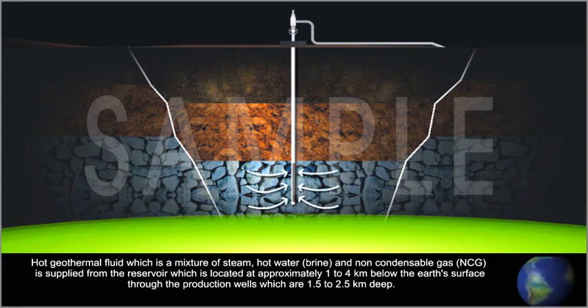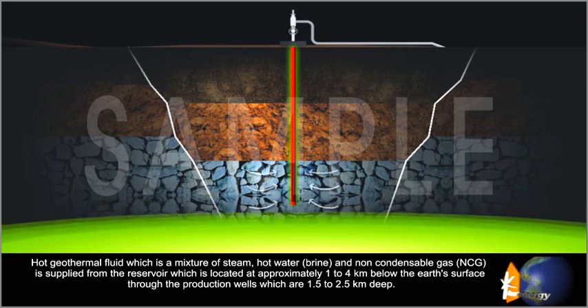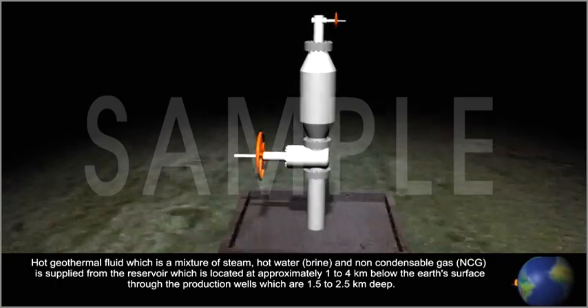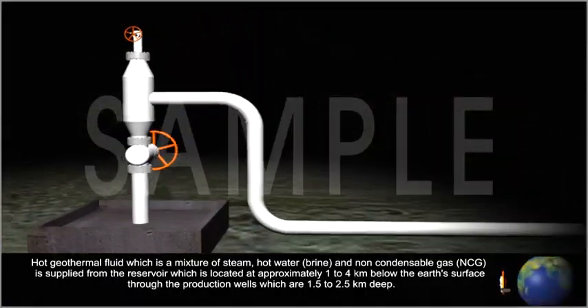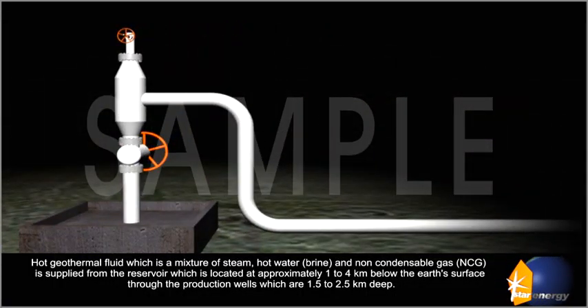Hot geothermal fluid, which is a mixture of steam, hot water, brine, and non-condensable gas (NCG), is supplied from the reservoir, which is located at approximately 1 to 4 kilometers below the Earth's surface, through the production wells, which are 1.5 to 2.5 kilometers deep.